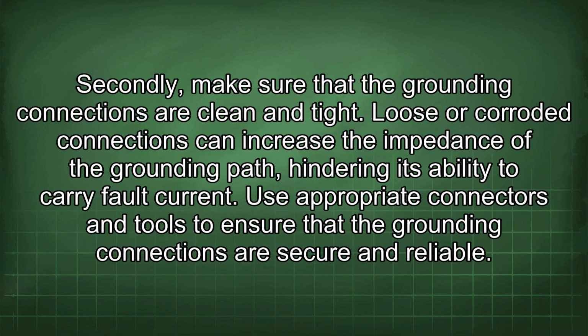Secondly, make sure that the grounding connections are clean and tight. Loose or corroded connections can increase the impedance of the grounding path, hindering its ability to carry fault current. Use appropriate connectors and tools to ensure that the grounding connections are secure and reliable.